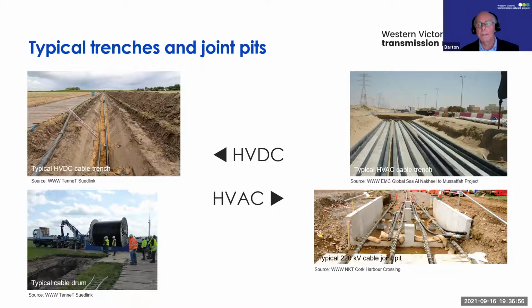On the right-hand side you see high voltage alternating current cables - three cables side by side, giving us one circuit or three phases. You can see a substantially wider trench is required with wider separation between the cables. Below that diagram is a typical joint pit, which has to be constructed about every 500 to 1,000 metres when implementing an underground technology solution.